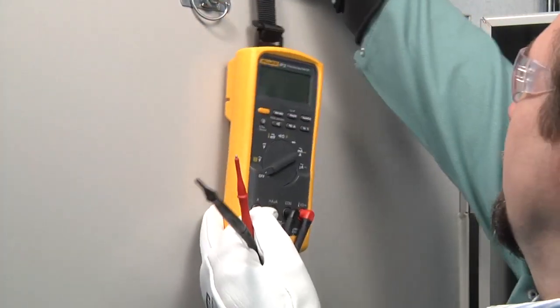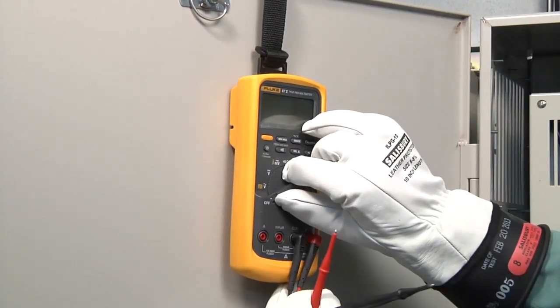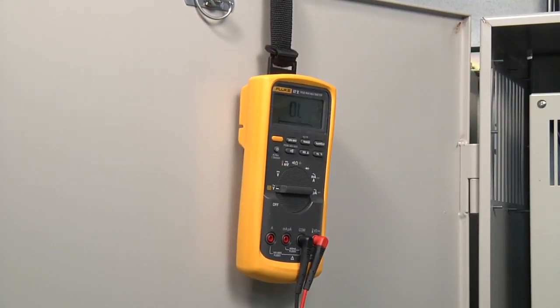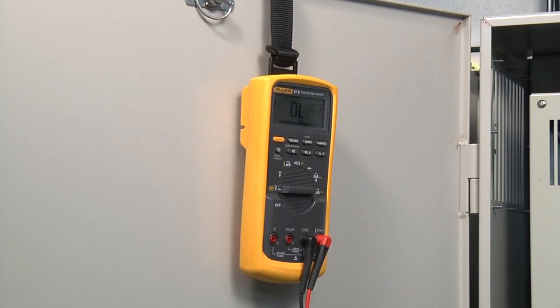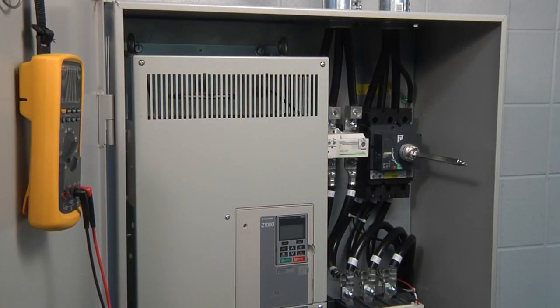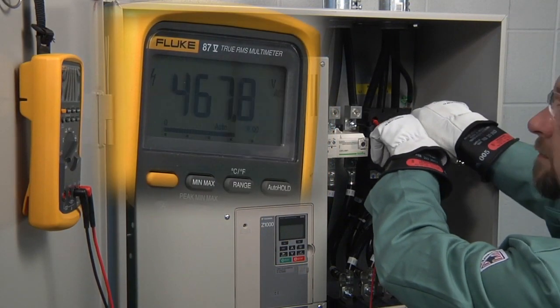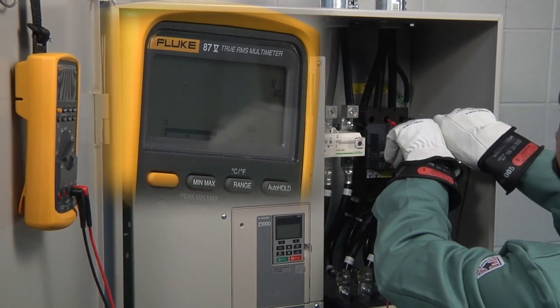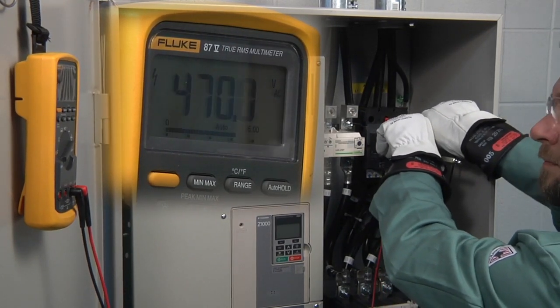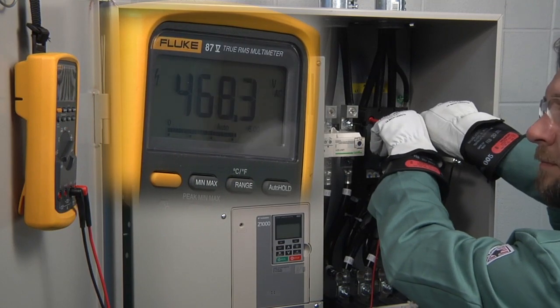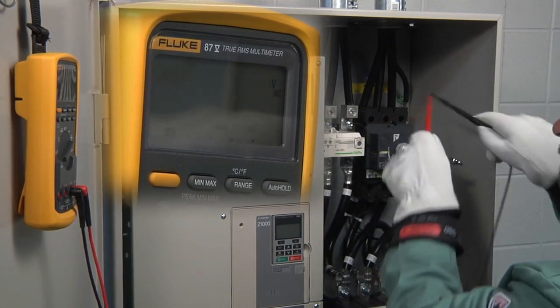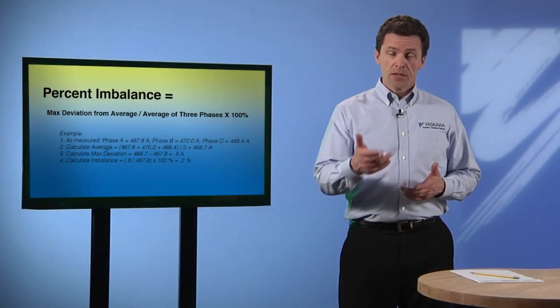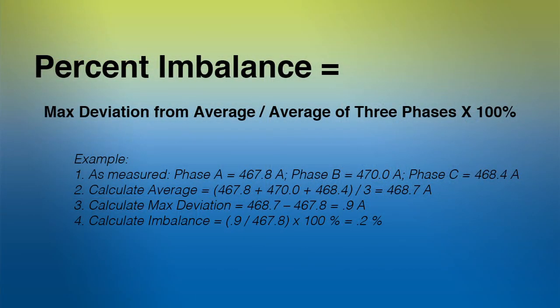Take out your multimeter and set it to volts AC, and we'll take a measurement phase to phase at the top or input side of the circuit breaker. We'll take a set of test measurements from L1 to L2, L2 to L3, and L1 to L3, looking for balance. The readings should be the same within a tolerance of approximately 1%. If you would like to calculate your percent imbalance, here's the formula.